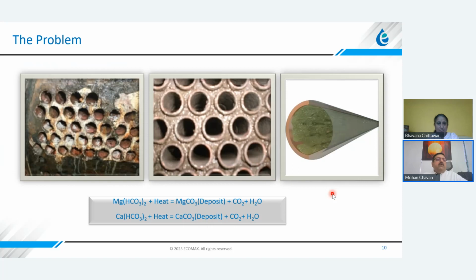Let's talk about the problem. What is the problem in the condenser? As I explained to you, there are magnesium and calcium bicarbonates present in the water. When they react in the condenser with the heat that is exchanged, there is a precipitation of magnesium carbonate and calcium carbonate, which will deposit inside the tubes. And that's where you will have an impact on the efficiency, because your heat transfer will not be proper. And the problem of scaling will be severe or less severe depending on the water quality that is maintained at various places.